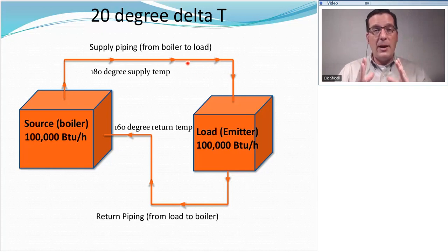So pay attention to your delta T, make sure it's within range, and realize that your delta T is directly related to flow rate through the boiler.